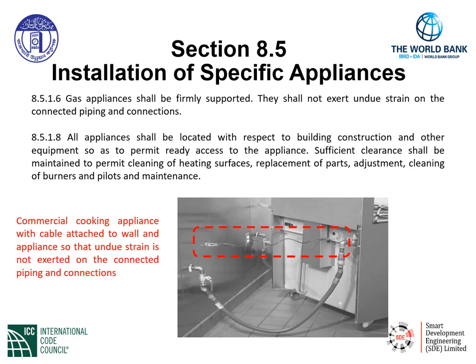The commercial cooking appliance is attached to a cable that fastens from the appliance to the wall, such that when workers are cleaning in back of the appliance, we do not put any undue strain on the appliance gas connector, as you can see here.